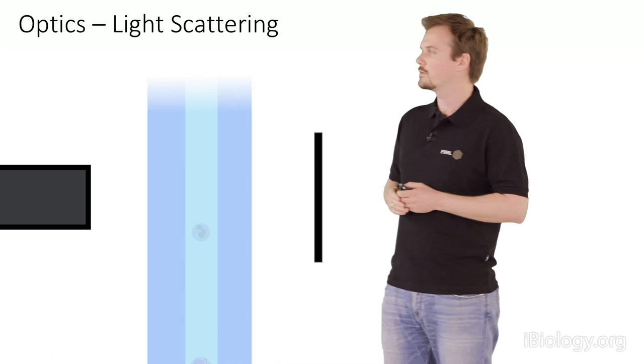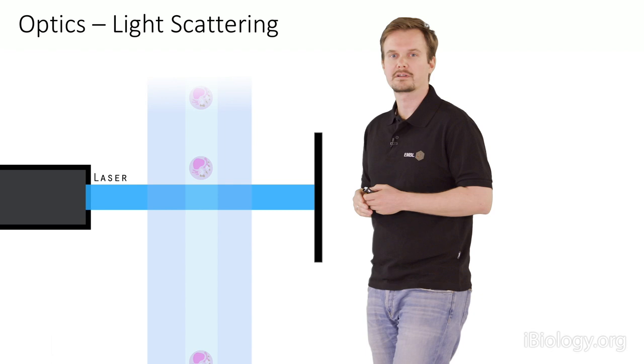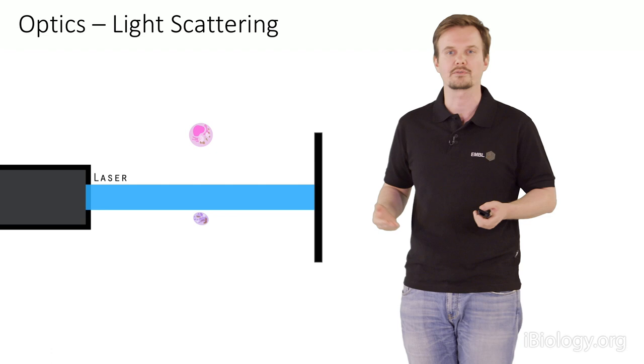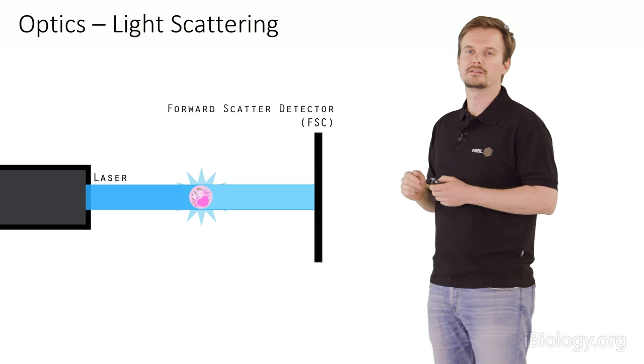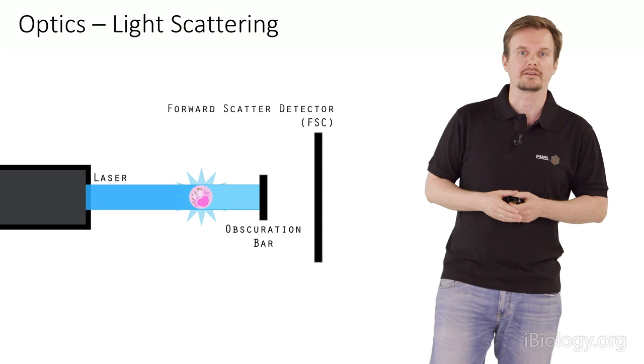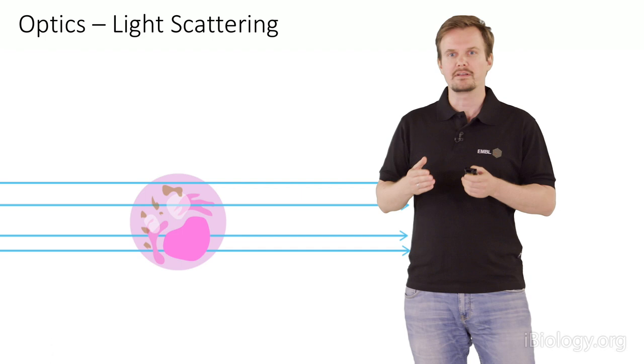Coming back to our setup: we have our fluid system and flow cuvette, into which we introduce our laser. With an optical instrument, our laser is tuned to the middle of the stream at the excitation maximum. This lets us detect the first parameter a flow cytometer generates: scattering of light. Light scattering is detected by a forward scatter detector — usually a photodiode. To avoid blinding it with the primary laser light, we use a so-called obscuration bar that blocks the primary beam.